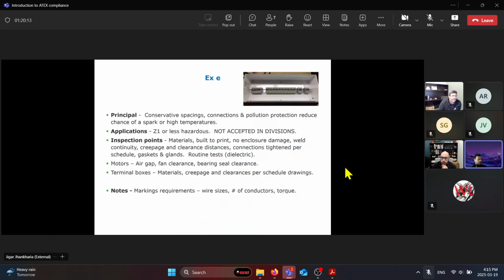And yeah, but just to quickly go over this, increased safety as a method of protection. The principle itself is conservative spacings, connections, and pollution protection that reduce the chance of a spark or high temperatures. Very similar to the non-incendive electrical equipment certification. If you read the scope for the CSA C22.2 No. 213 binational standard with the UL 1201 that your current product is certified to, it's very identical, I would say, in that sense. Except when you get a product certified for increased safety, it is not accepted in division, and vice versa. When you have a product certified for non-incendive, we can accept it directly for zone requirements.